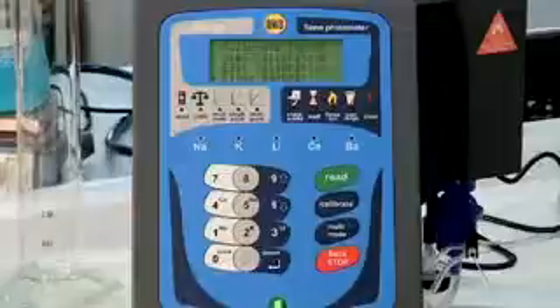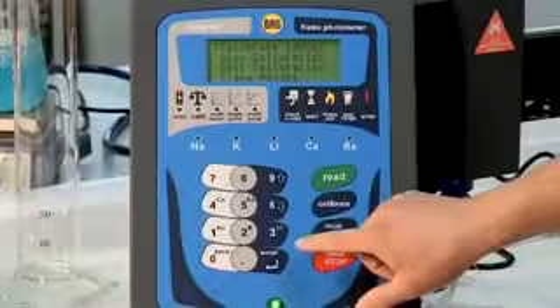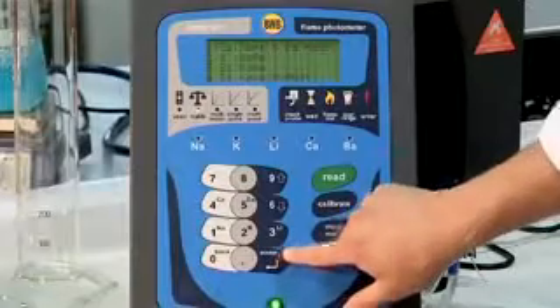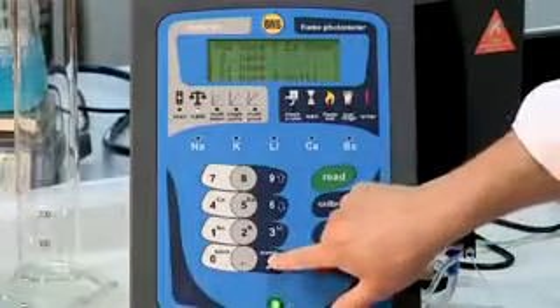The BWB XP offers the user a multiple ion, multi-point calibration. For this calibration, three ions will be used, sodium, potassium and lithium, at three different concentrations. Standard 1 has 90 parts per million sodium, 40 parts per million potassium, and 10 parts per million lithium. Standard 2 has 100, 50, and 20 respectively. Standard 3 has 110, 60, and 30 also respectively.